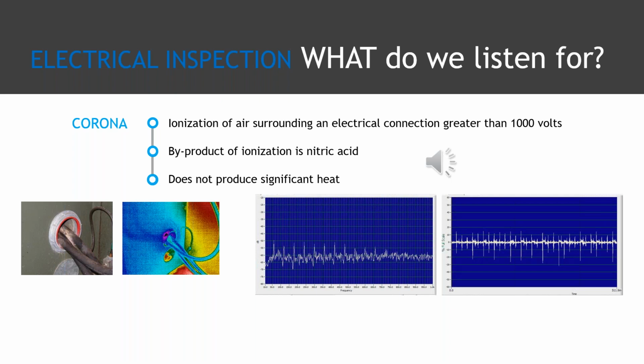And what we typically would expect to see on a time waveform or on a spectrum is we'll see 60 cycle harmonics, but we'll see a lot of frequency content in between. And on the time waveform, we'll also see pretty evenly spaced discharges and pretty even height of the discharges. And a steady state, sort of a buzzing sound is what we'll expect with corona.